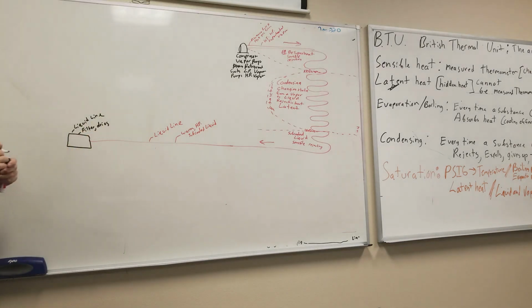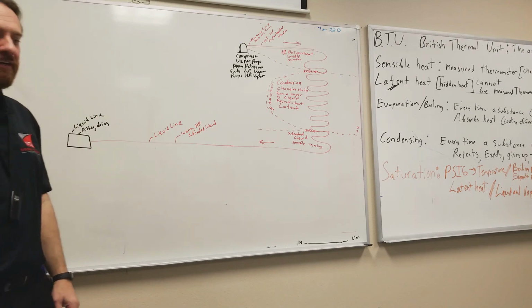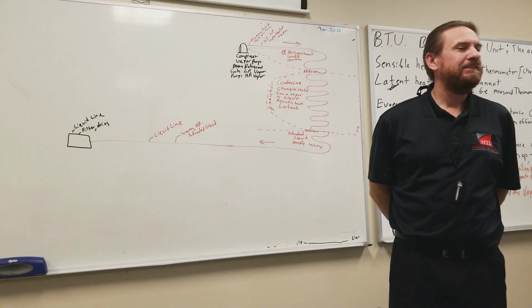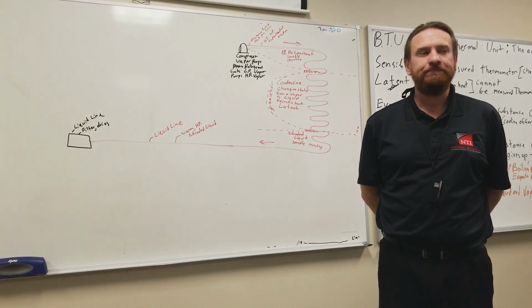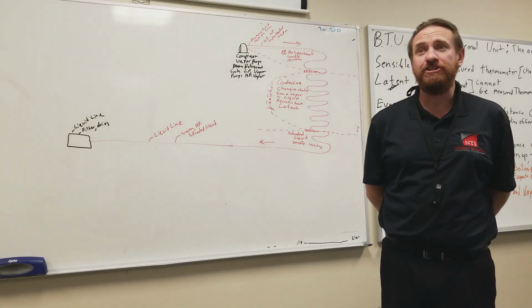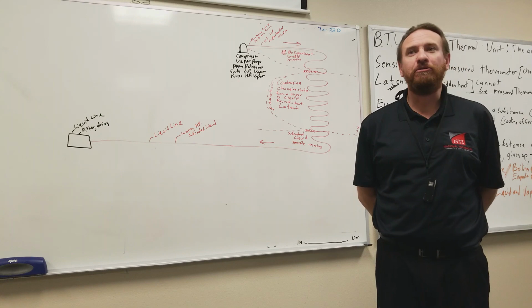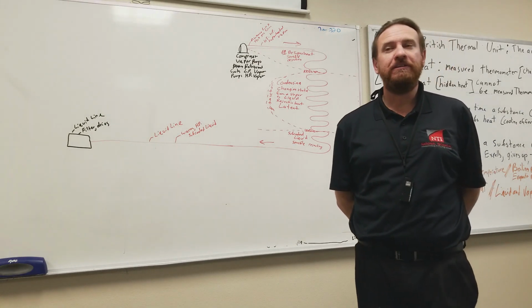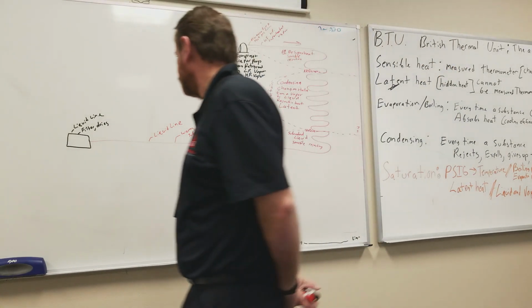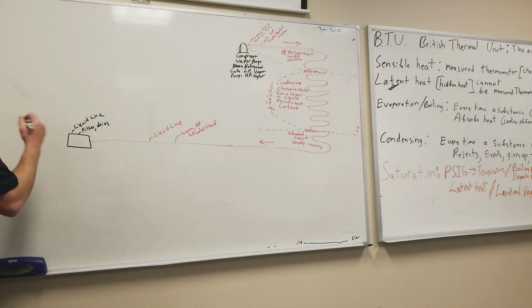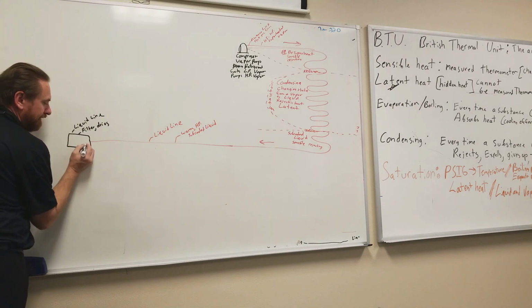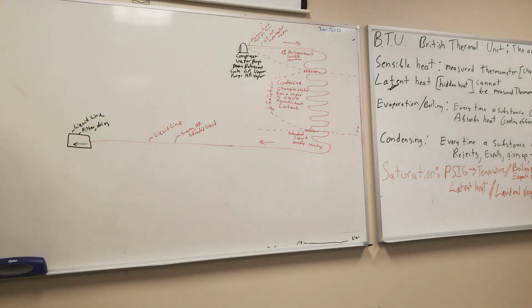What is it drying? What is the dryer part doing? Moisture, H2O. There's a difference between liquid and water. Water is in liquid form, but water is water. We could have liquid nitrogen. Is that the same thing as liquid water? No, they're both liquid, but they're different chemicals. The arrow on this filter dryer should point in which direction? Away from the condensing unit and towards the metering device. Yep.